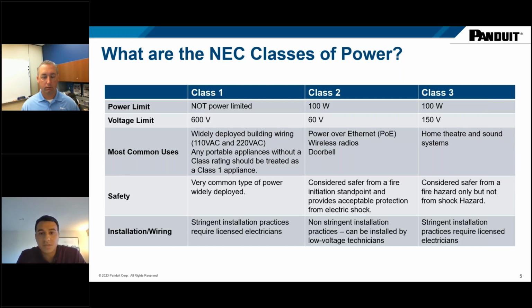Class 3 is very similar to Class 2, limited to 100 watts. However, it has a voltage limit of up to 150 volts. Most common application is home theater and sound systems, and it is considered safe from a fire hazard standpoint, but not from a shock hazard, and therefore you still have to have electricians install it.